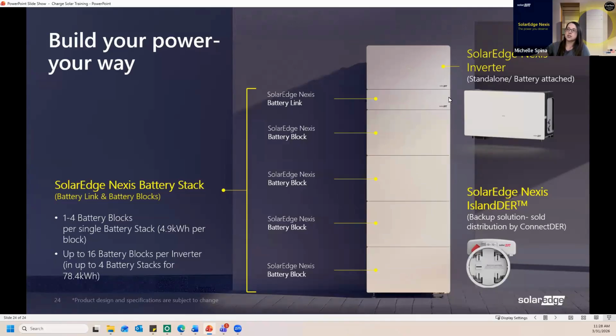And then this link is actually the communications device between the inverter and the battery block. So each stack that you have, so if there's 4 battery blocks here, each stack that you have needs a link, but you can actually, per inverter, have 4 stacks of batteries, which would be 16 battery blocks and up to 78.4 kilowatt hours. So very large capability with this unit, even on just one inverter.